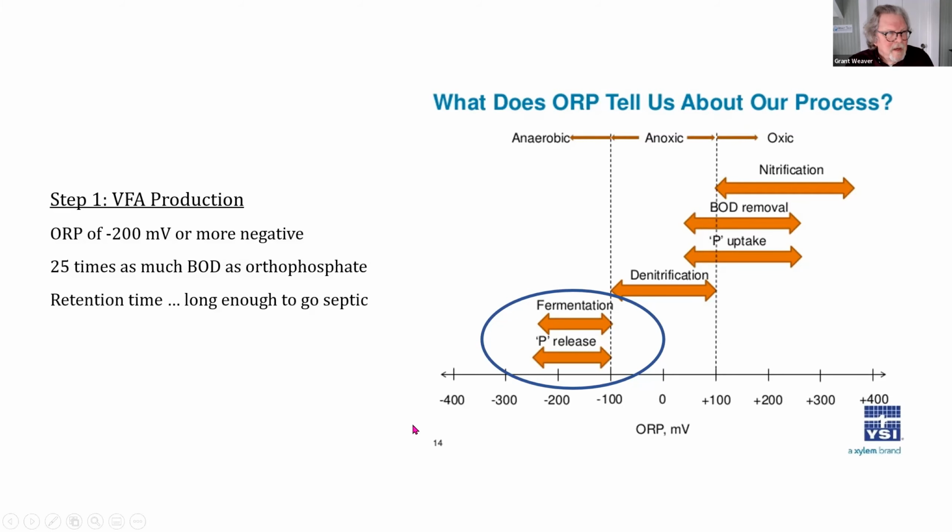Look at this one. Now we're really going to be BOD limited. We're trying to do both nitrogen and phosphorus, and we have a great pre-treatment program and really effective primary clarifiers. Very few SBRs have primary clarifiers. In fact, in my experience, I've seen zero that have primary clarifiers. But we need the BOD for phosphorus removal.